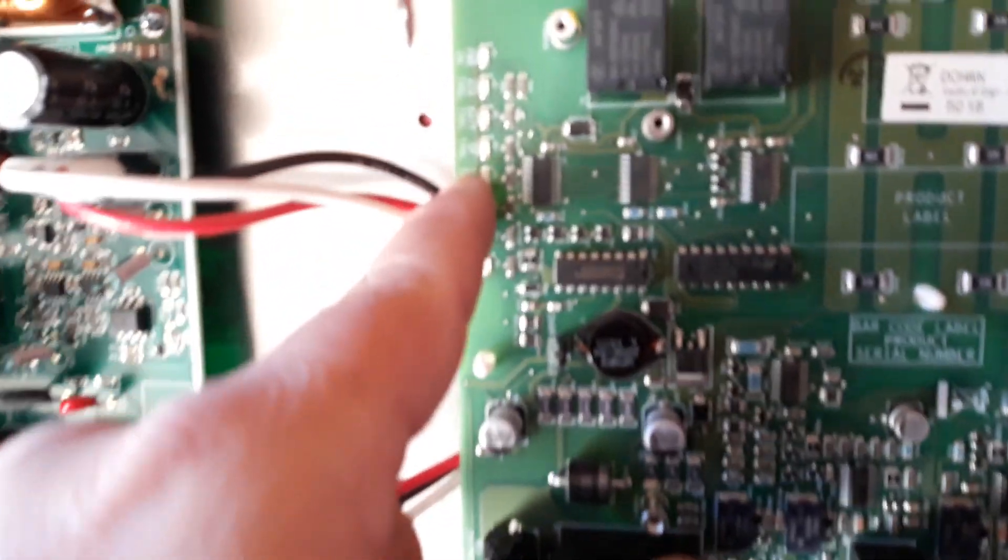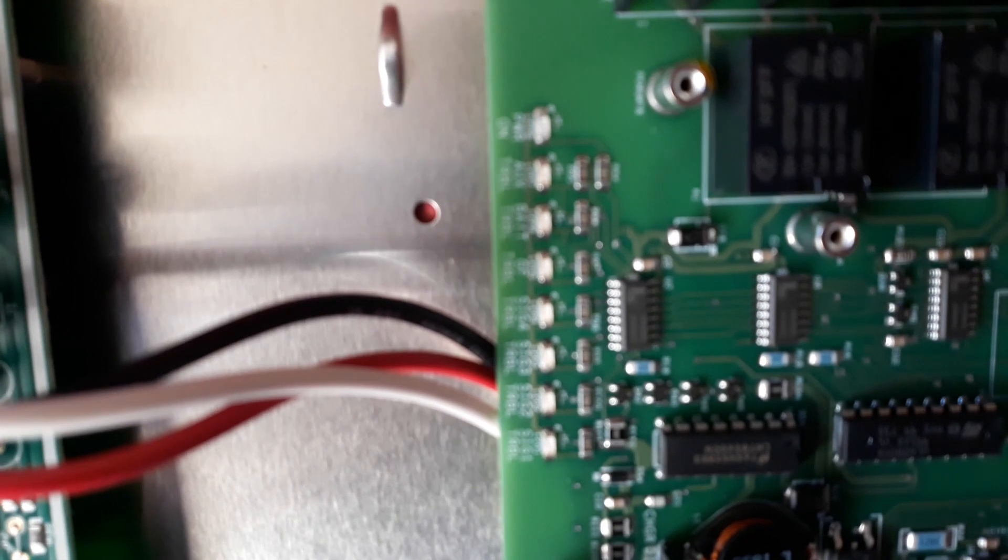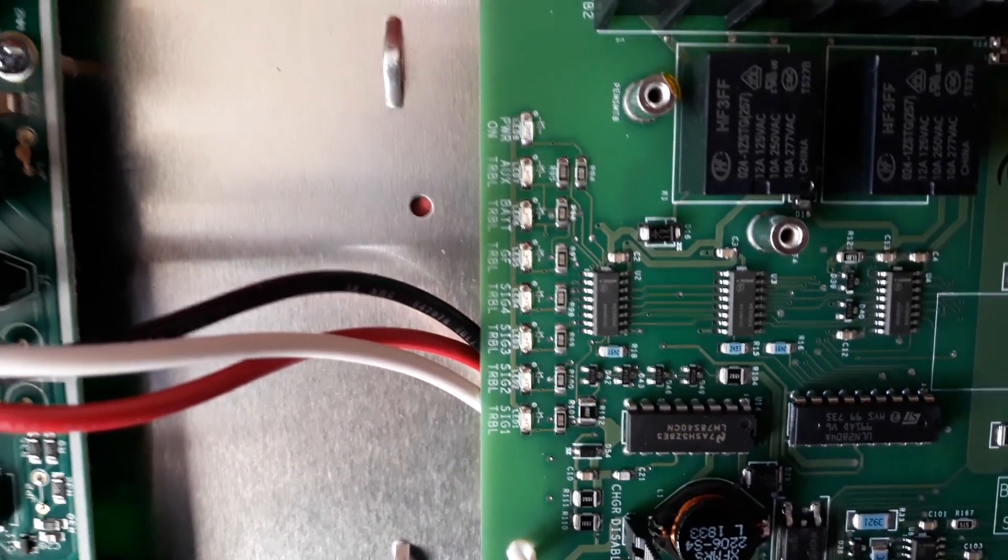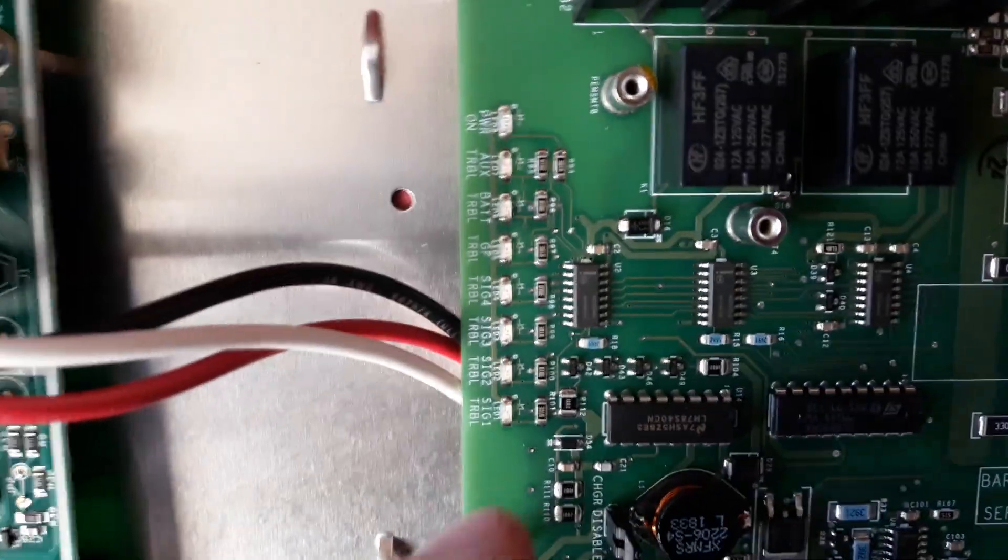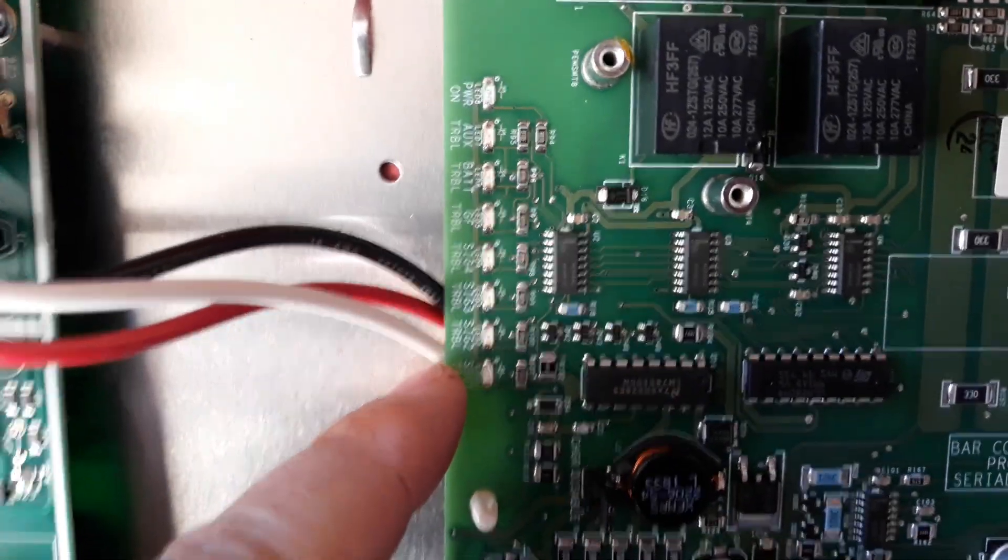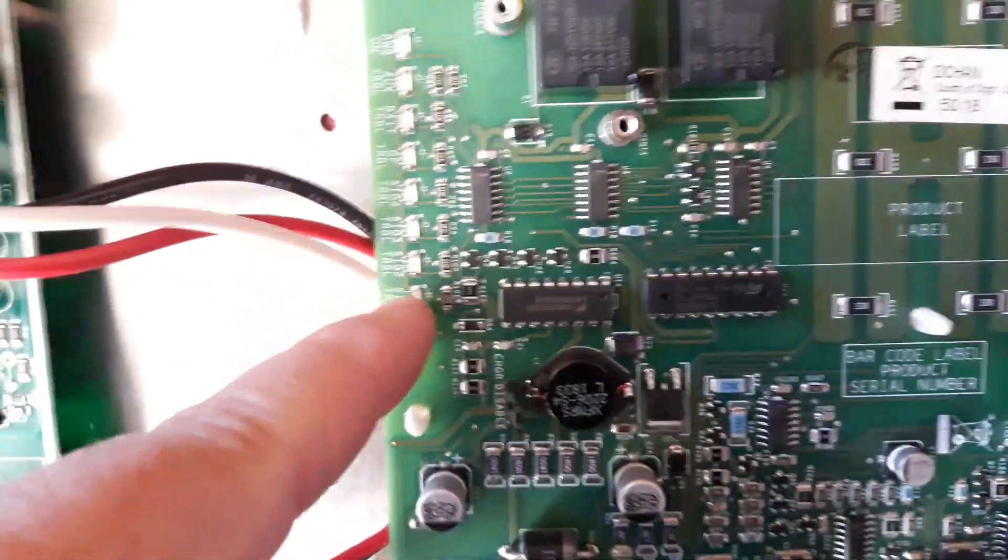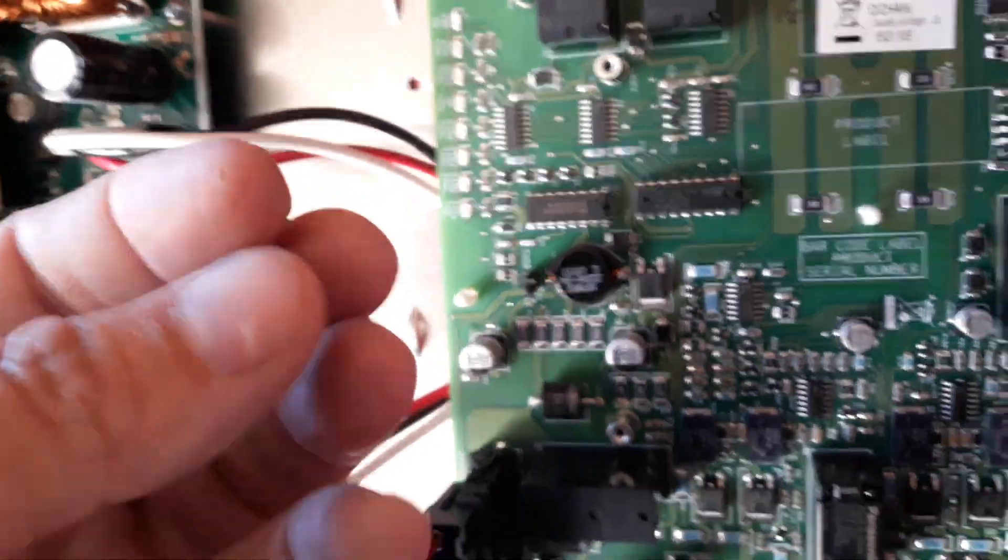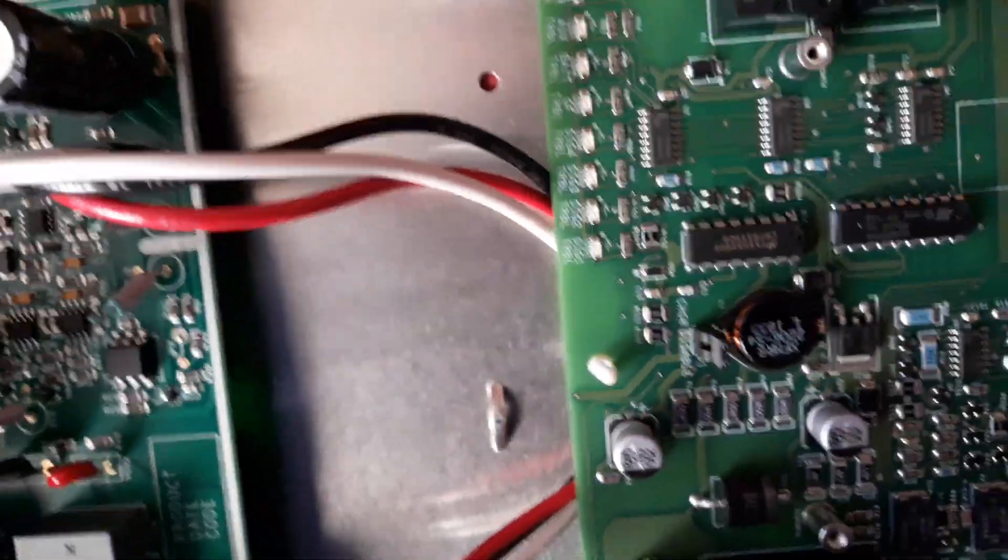I like that feature a lot. Over here, so if there's a trouble on here on these LEDs, and the trouble is an intermittent trouble. If one of those has an intermittent trouble, whenever you come out here, instead of it showing a normal panel, where you had the trouble will be blinking. So you know that's the circuit that had the trouble on. So you can go out there in the field and start looking on that circuit.